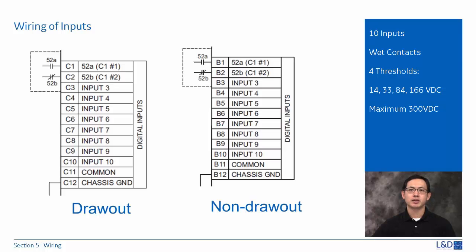The inputs should be connected to the positive terminal of an external DC power supply. The negative side of the external source must be connected to the relay's DC negative rail at terminal C11 for drawout type and B11 for non-drawout type.